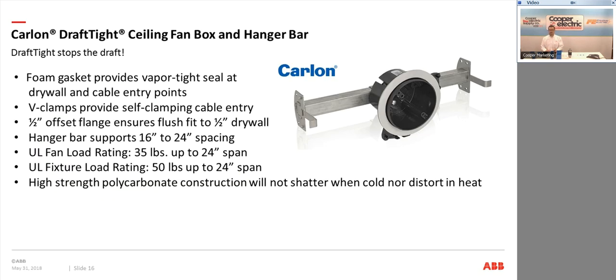In addition to the electrical boxes, we also have them in ceiling fan boxes. Your typical ceiling fan box has a hanger bar supported at 16 to 24-inch spacing. These boxes also have foam gasket seals on the front flange and the back side for the cable entry points, with integral V-clamps on the inside to provide a self-clamping cable entry point. They're UL rated for a load rating of 35 pounds up to a 24-inch span, and a UL fixture load rating of 50 pounds up to a 24-inch span.